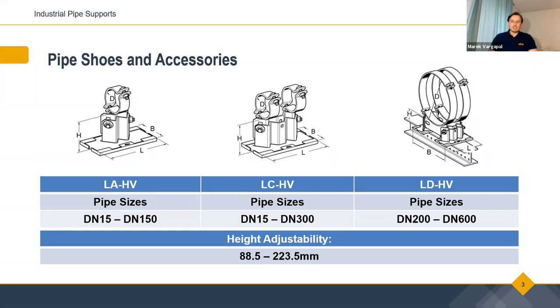It's specifically stainless steel Mapress pipes, which I'm sure you are aware, they have different outside diameters than what we are used to in industrial piping, for example. So we had to look into our clamping ranges, select the right clamps, and dedicate a range to those. I can say honestly that between the diameters DN15 and DN100, which is the Mapress stainless steel range, we can cover all pipe sizes. So that's not a problem. And that's also implemented in our software, which my colleague Alicia presented earlier.